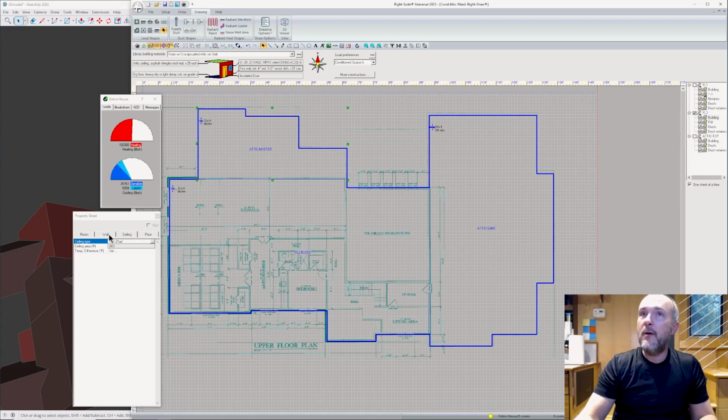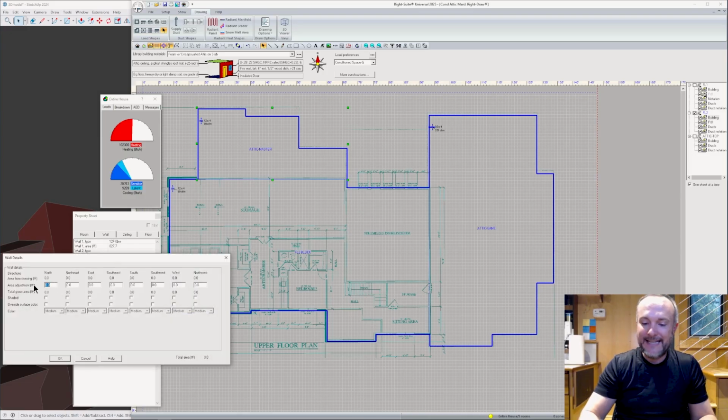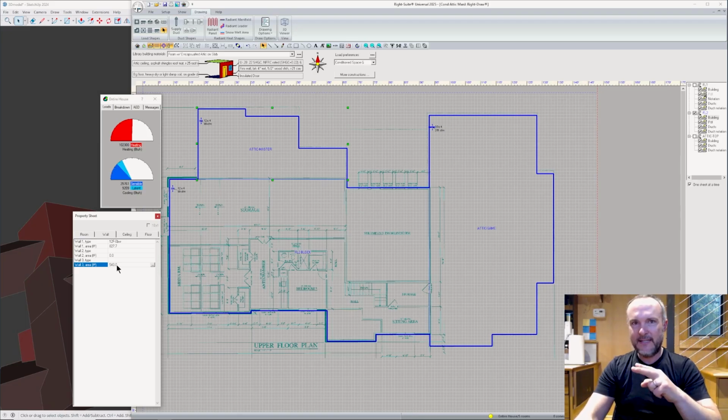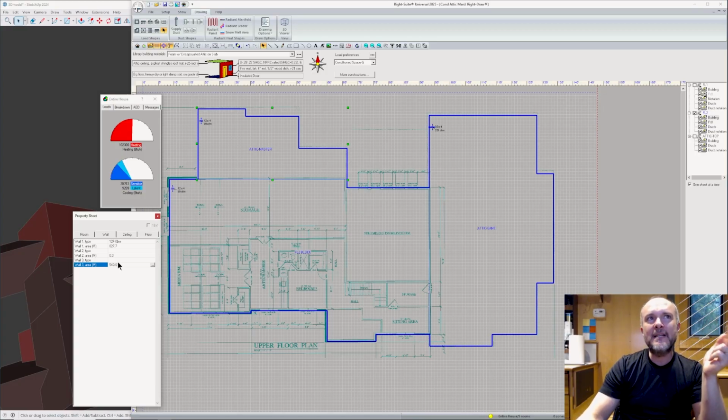Now we come to the third wall type. The third wall type is here, and I'm going to add that 540 square feet to it. So now I have wall 3 being 540 extra feet that was not accounted for in my ceiling. Wall 3 is very interesting because it is assignable. It can be whatever you want it to be. So this is a very specific Wrightsoft thing. How I want to build this library item, this component of wall 3, what is it?